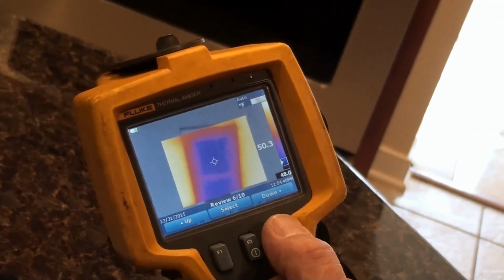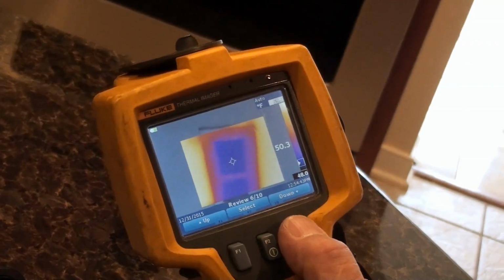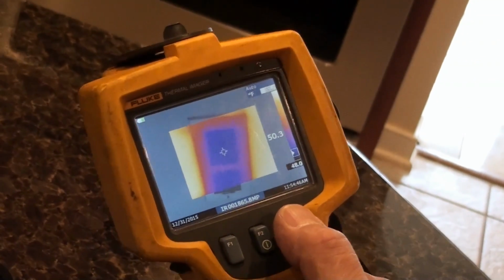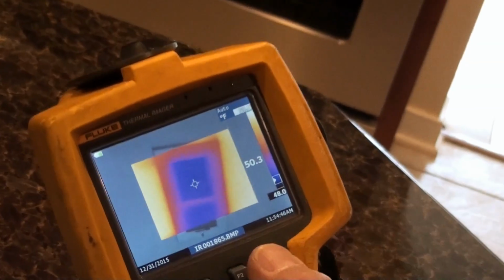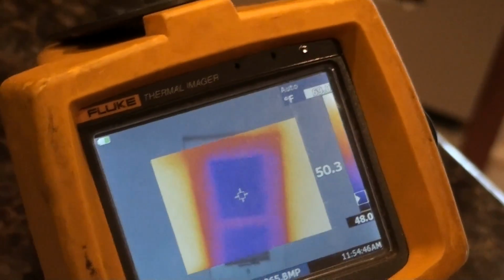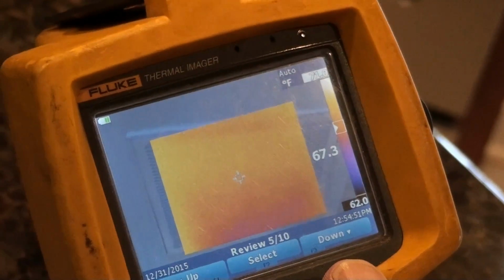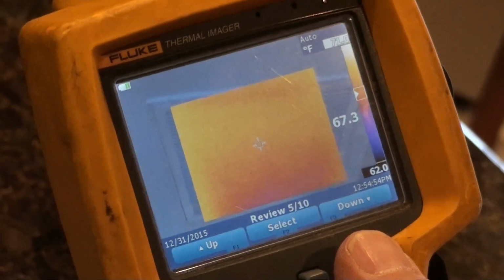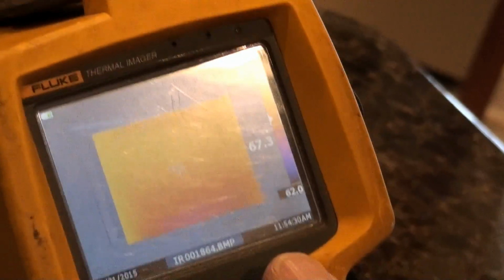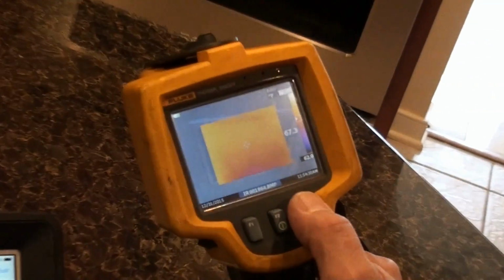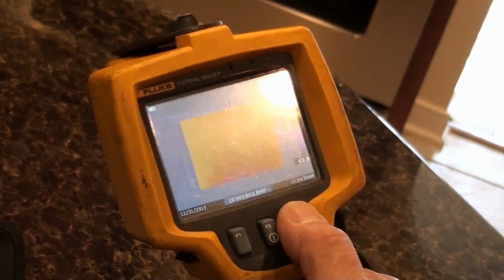Okay, this was in the air conditioning mode, and you can see I'm getting 48 degrees coming out of the supply, and I'm getting 67 going into the return, so that's a 19 degree difference. 16 to 20 degrees is considered adequate, so the system is working properly.